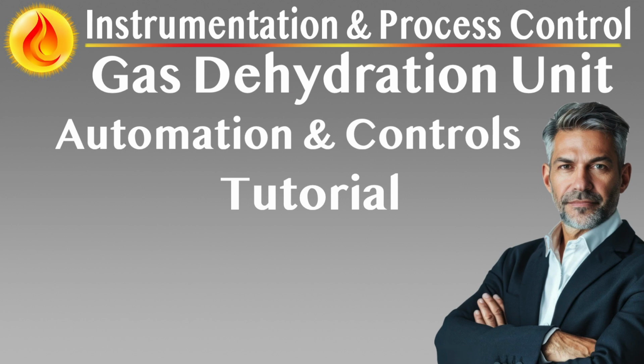Steam heating. Steam control valve modulates based on reboiler TT and steam pressure control. Condensate is returned to the utility system with level monitoring in the steam trap. Electric heating. Thermocouple-based PID controller governs electrical input. Over-temperature protection includes dual safety thermocouples and redundant contactors.